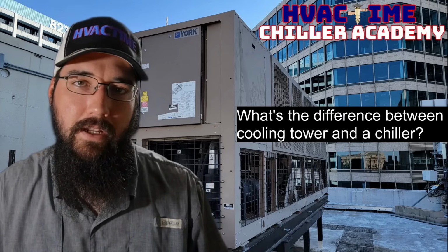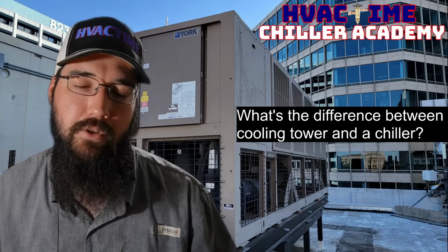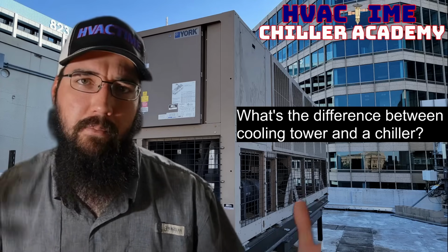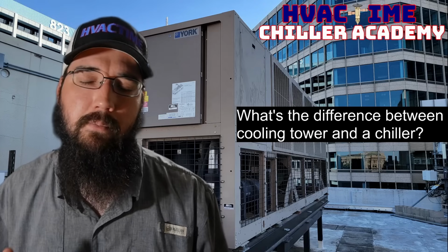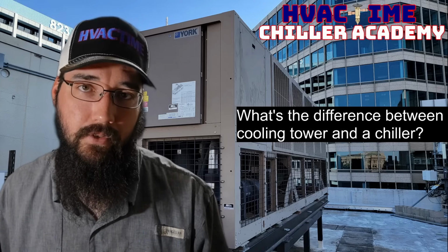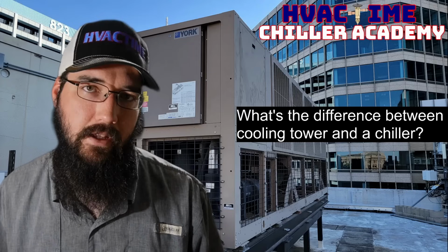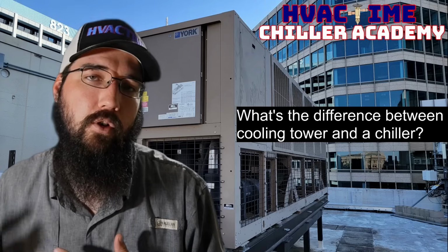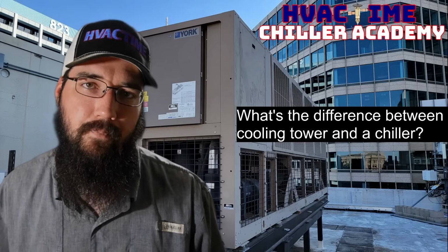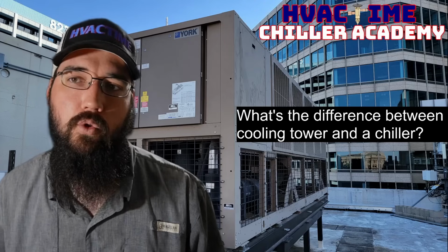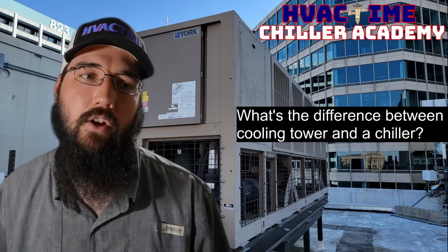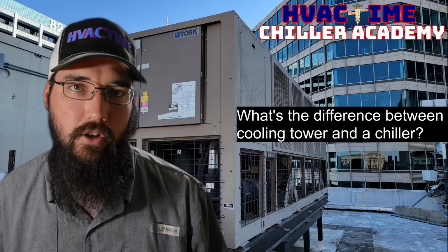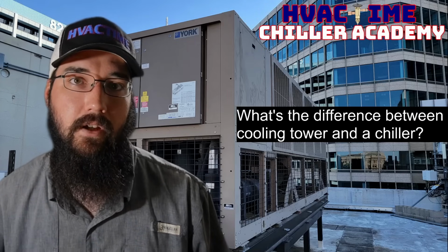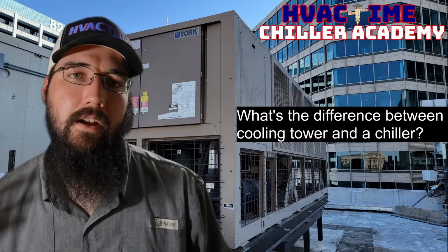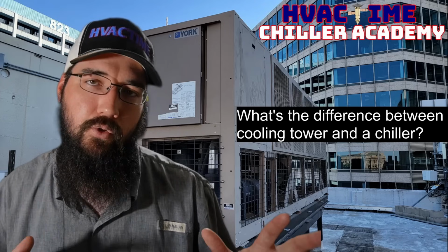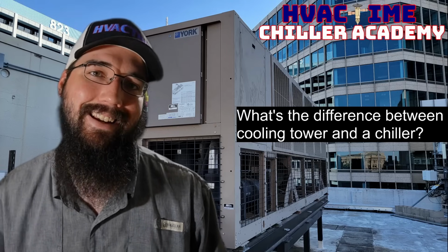Now, this scales from teeny little process chillers that might cool a CT machine all the way up to the biggest of the centrifugals that exist out there. So that is my basic definition of a chiller. Now, cooling towers are used on a variety of applications. In a chiller context, we use it to cool our condenser water. So we have a water-cooled condenser that we're flowing through. Now, when we say water-cooled, it could still be a brine mixture, meaning that it has some kind of glycol or other non-freezing agent included, so it can run at lower ambients safely. But we'll have something like that running through the chiller to take the heat away, and the cooling tower will specifically be located outside to reject that heat.